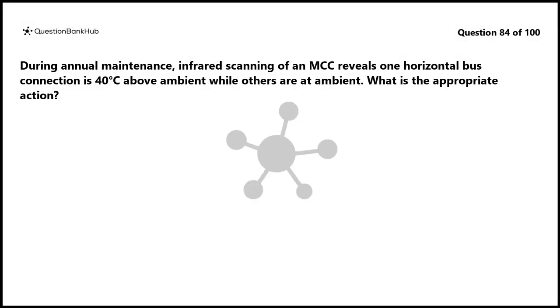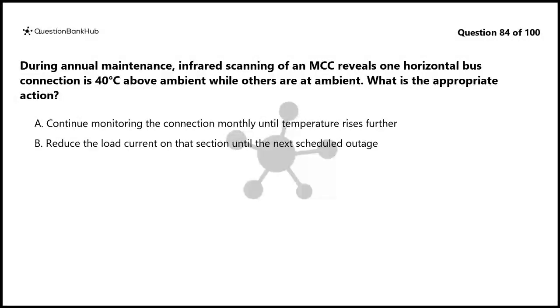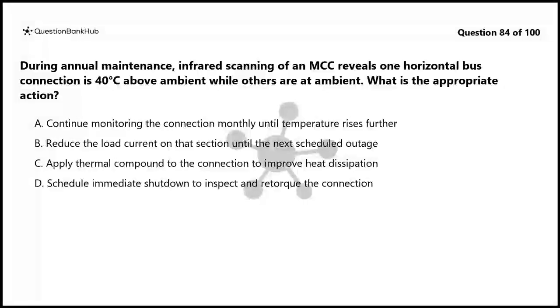Question 84. During annual maintenance, infrared scanning of an MCC reveals one horizontal bus connection is 40 degrees Celsius above ambient while others are at ambient. What is the appropriate action? A. Continue monitoring the connection monthly until temperature rises further. B. Reduce the load current on that section until the next scheduled outage. C. Apply thermal compound to the connection to improve heat dissipation. D. Schedule immediate shutdown to inspect and retorque the connection.